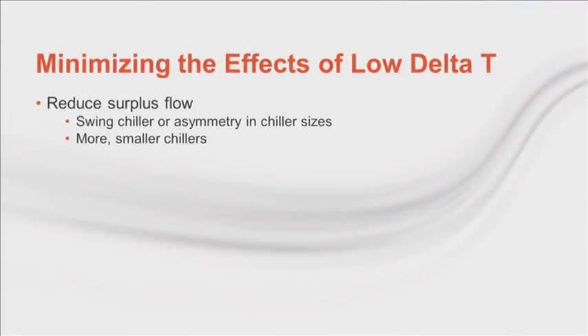One of the effects of low DeltaT is extra pump energy. So you're wasting energy on the primary and the secondary side in this system. One option is to reduce primary pump energy to right-size the operating chillers to meet the load, and therefore reduce surplus flow. This could include a swing chiller that's smaller than the others, or more smaller chillers, installed to more closely match load, and I mean flow, and limit the surplus flow in the bypass pipe. By putting a smaller chiller in the lineup, the controls will stage the smaller chiller on and off again before adding a larger chiller. This could also mean installing 3 chillers instead of 2.